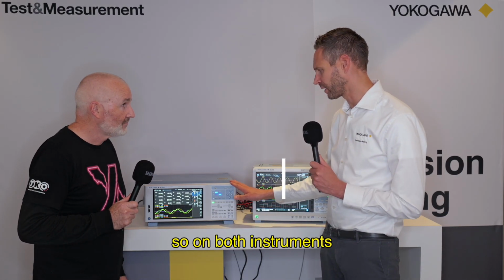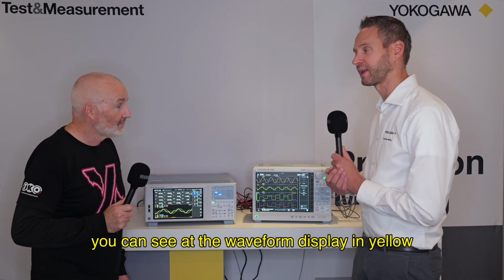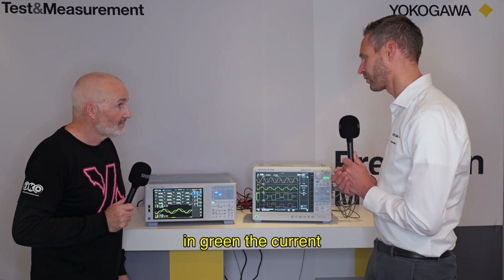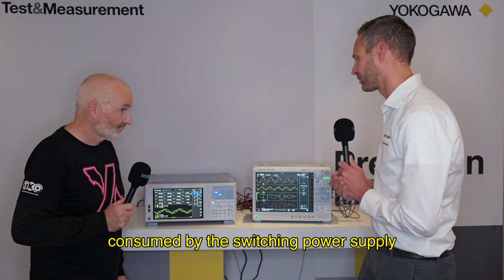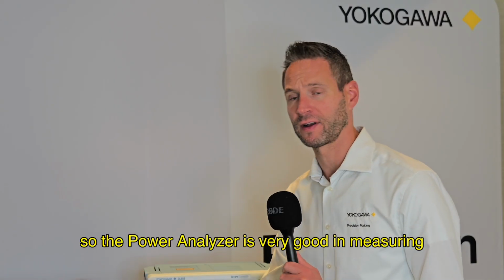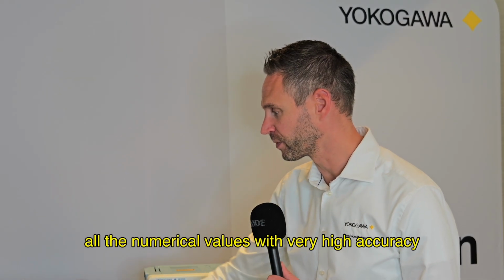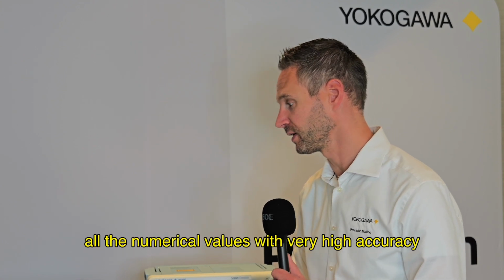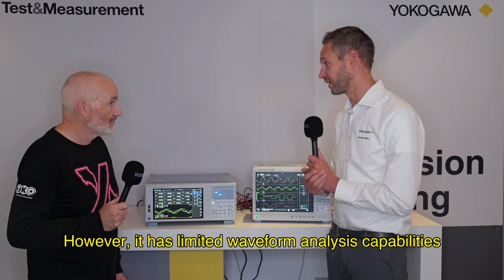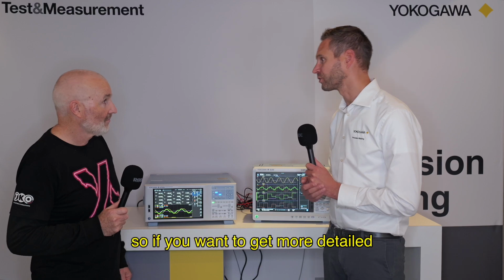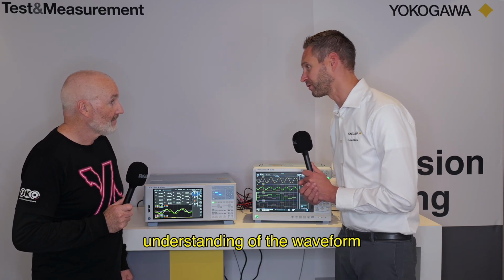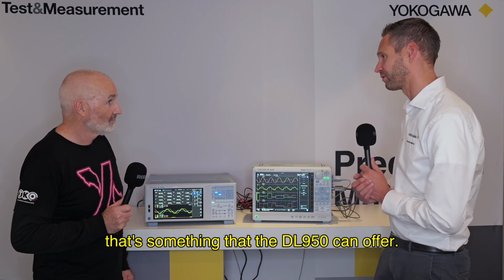So on both instruments you can see at the waveform display in yellow the voltage and green the current consumed by the switching power supply. So the Power Analyser is very good in measuring all the numerical values with very high accuracy. However, it has limited waveform analysis capabilities. So if you want to get more detailed understanding of the waveform, that's something that the DL950 can offer.